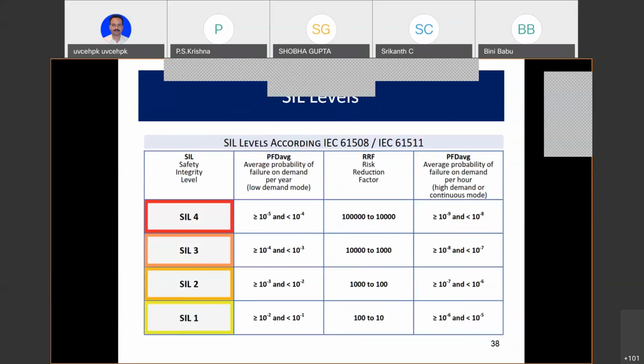Now, I'm bringing you into some figures. So far we are talking about SIL, and I was very loosely saying that it's got a reliability stamp, how reliable the safety system is. The SIL is an indicator. What does it contain? SIL 4, the highest, the gold-plated one. We'll go to high demand and low demand, I'll explain. When you say demand, you go back to your sketch, and in that sketch, you saw that the command comes because reactor pressure is high, higher than 30. Please shut. That is the process demand we are talking about.